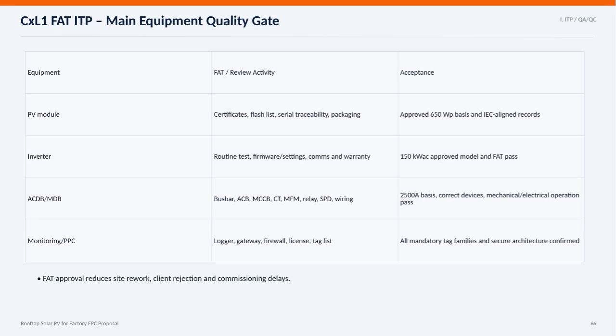Here we have the main equipment quality gate for the factory acceptance test, or FAT, in our rooftop solar PV proposal. The table highlights key equipment and their respective FAT or review activities alongside acceptance criteria. For the PV modules, we verify certificates, flash lists, serial traceability, and packaging. Approval is based on a 650 watt peak standard and adherence to IEC records. Inverters undergo routine testing, including firmware checks, communications, and warranty validation. Only models approved for 150 kilowatts AC and those that pass FAT are accepted.